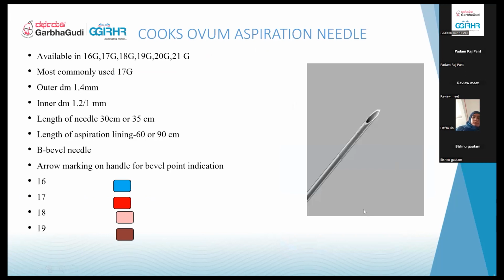Cooks, which are most commonly used. As I said, they are color coded based on the gauge. What we use is the red color, that is the 17 gauge needle. The length of the needle is around 35 centimeters. The outer diameter is 1.5 and the inner diameter is around 1 millimeter. The length of the aspiration tubing varies between 60 to 90 centimeters. They are bevel needles.